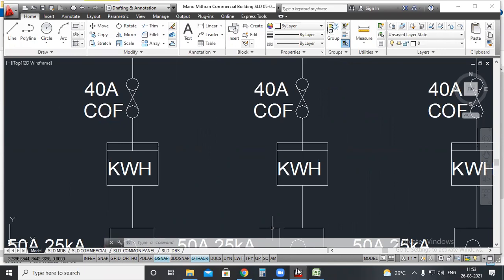We were discussing the tampering of electricity. Until the energy meter, we cannot take the cable underground as per the Kerala standards or KSEB standards. So we need to make sure that the energy meter's location is okay with this particular client, so that the cable will be visible from the energy meter to his building.